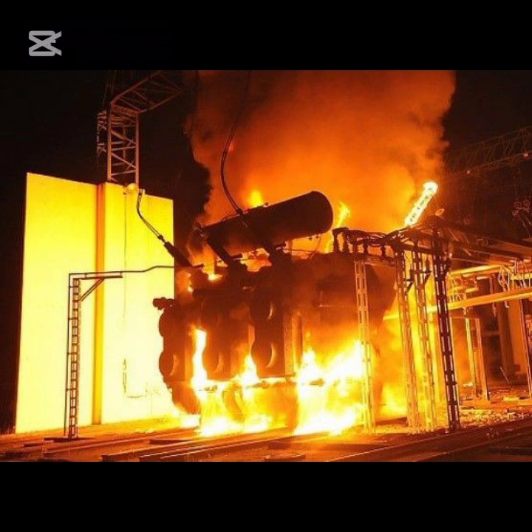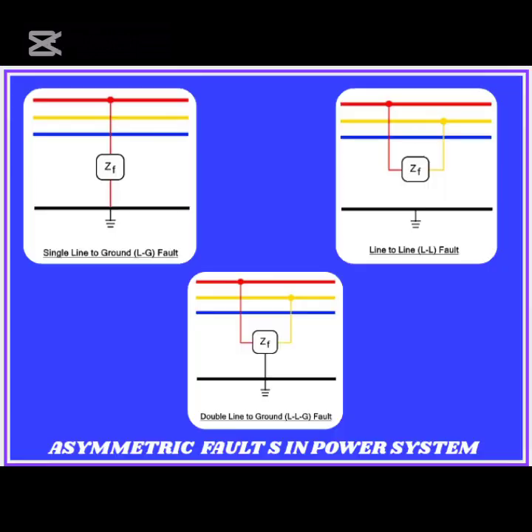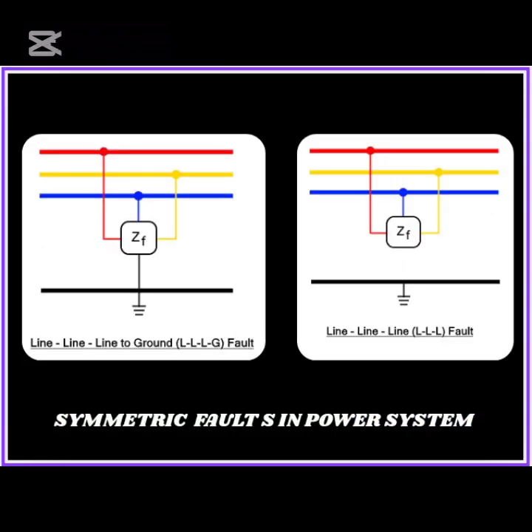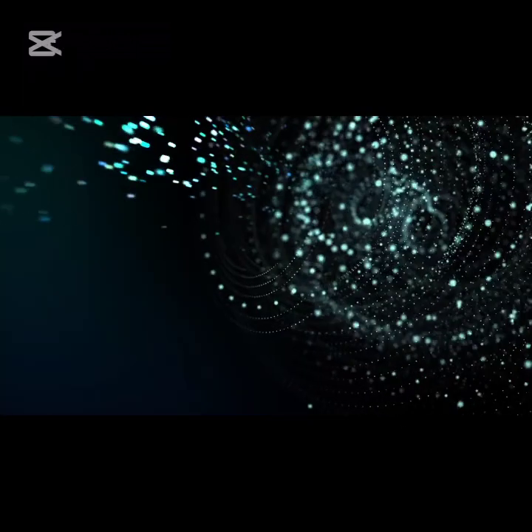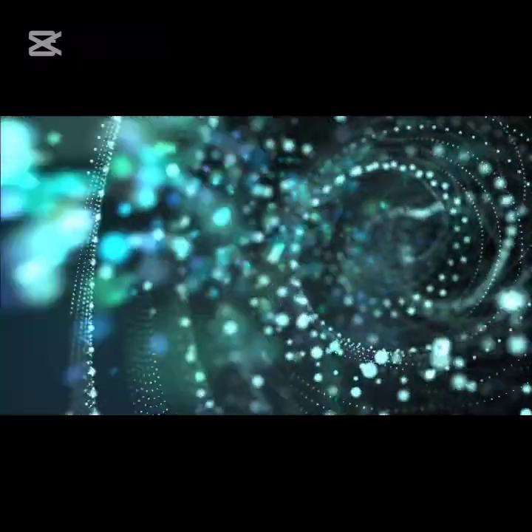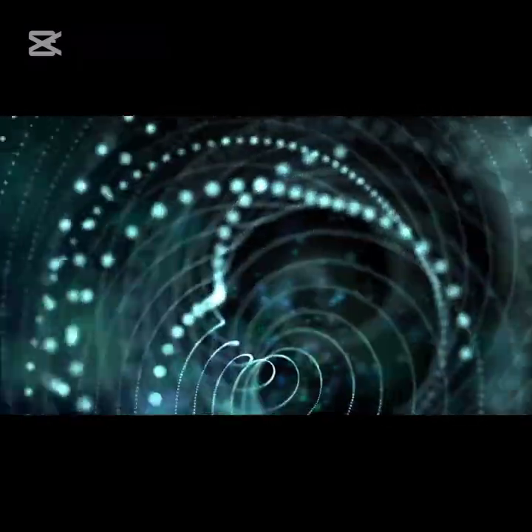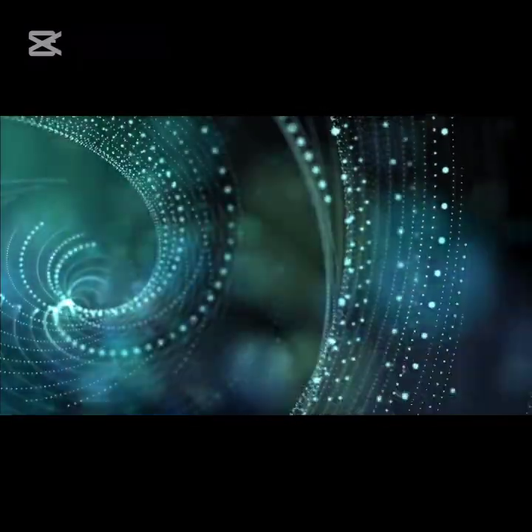Now, as we have understood all the short circuit faults, note that number 1, 2, 3 faults are called asymmetric faults because they do not affect all the phases at once, causing unbalanced fault currents. Then, number 4 and 5 faults are considered to be symmetric faults because they affect all phases equally, resulting in balanced fault currents. Since we have understood what short circuits are, let us delve into their effects on power systems. Here are the effects of short circuits on power systems.